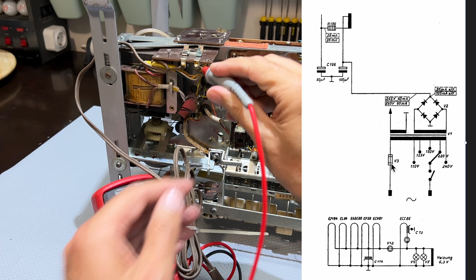And there's my problem, one of my problems. You see this resistance running around there? That should be almost zero. The reason is this contact here is very dirty, so we've got to clean that first.